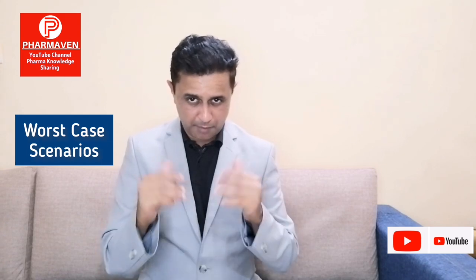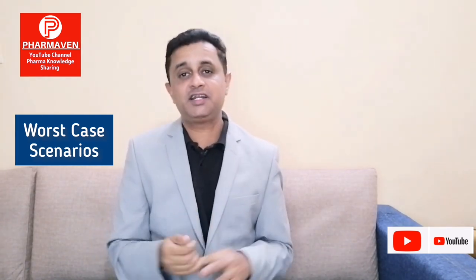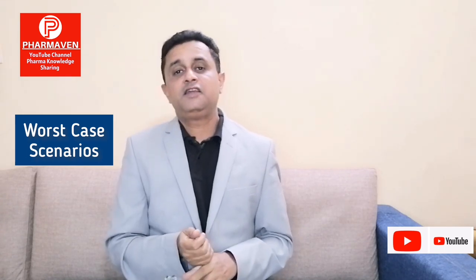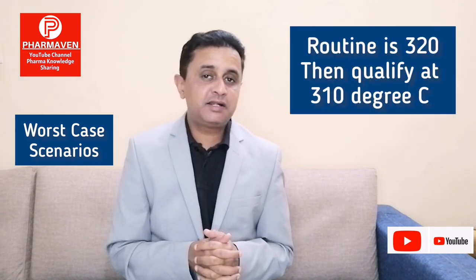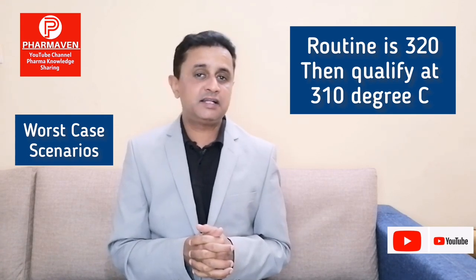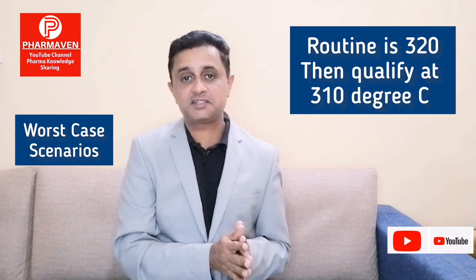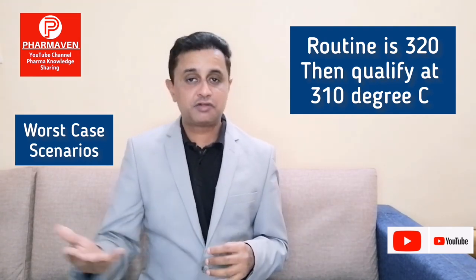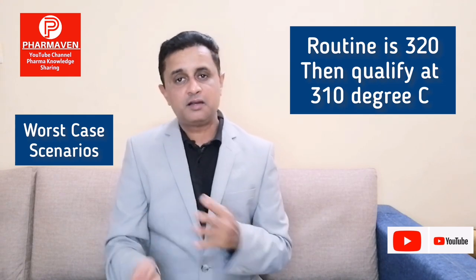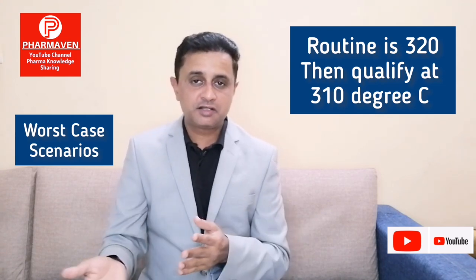So in a normal scenario, how do we apply the parameters? For the tunnel sterilization qualification, we have to select the worst case scenario in terms of temperature and time. For example, if my routine temperature for the tunnel is 320 degrees, then I have to qualify it at 310 degrees, which is 10 degrees Celsius lesser than my set temperature for routine operation. This is not a standard and can vary from company to company, but it is good practice that we qualify at a lesser temperature than what we use for actual operation.